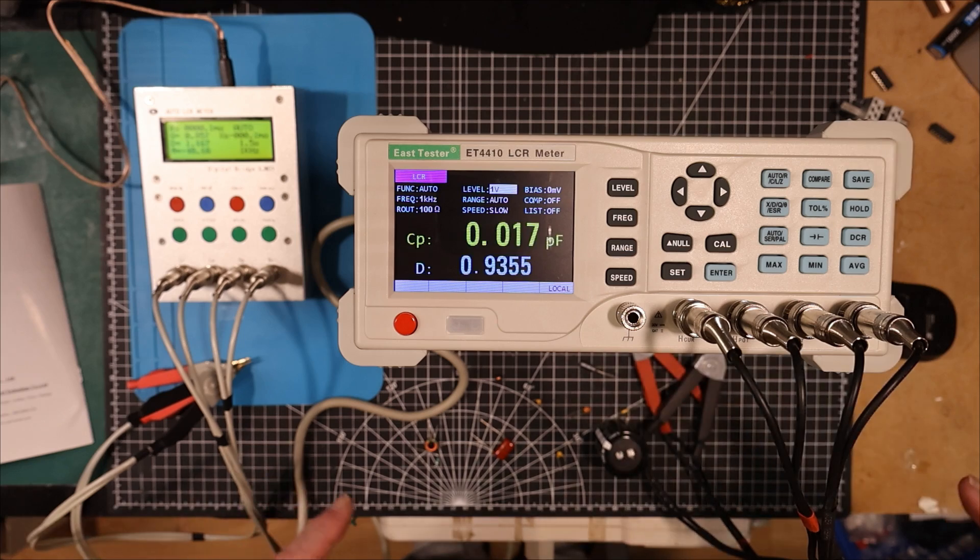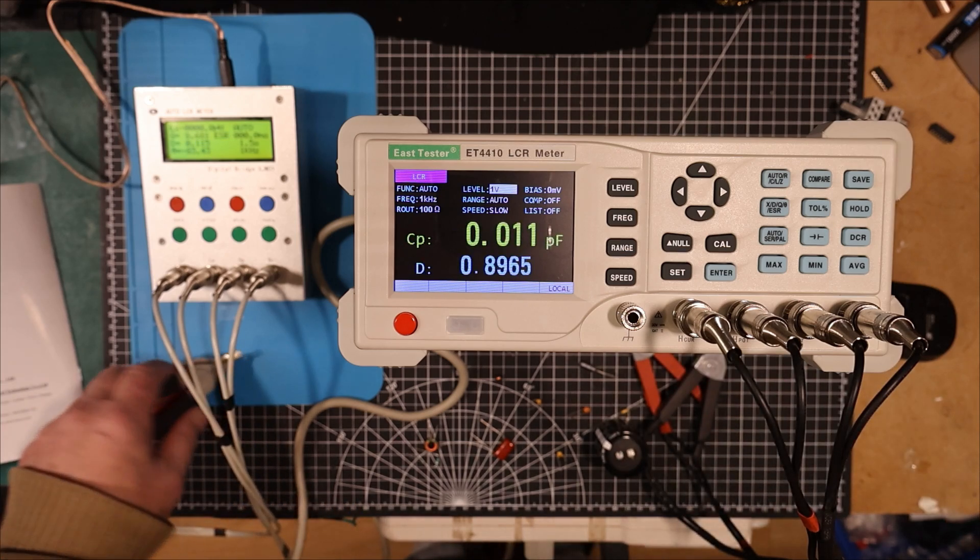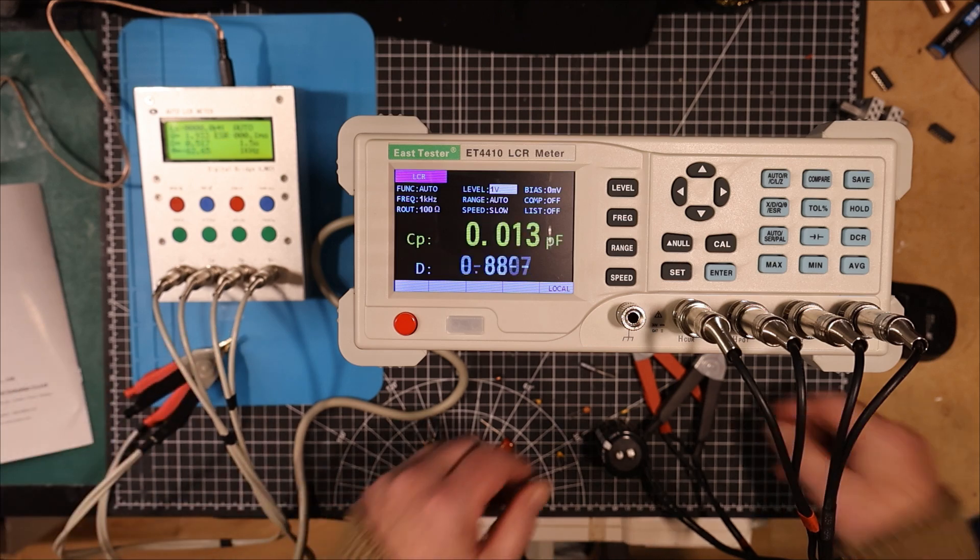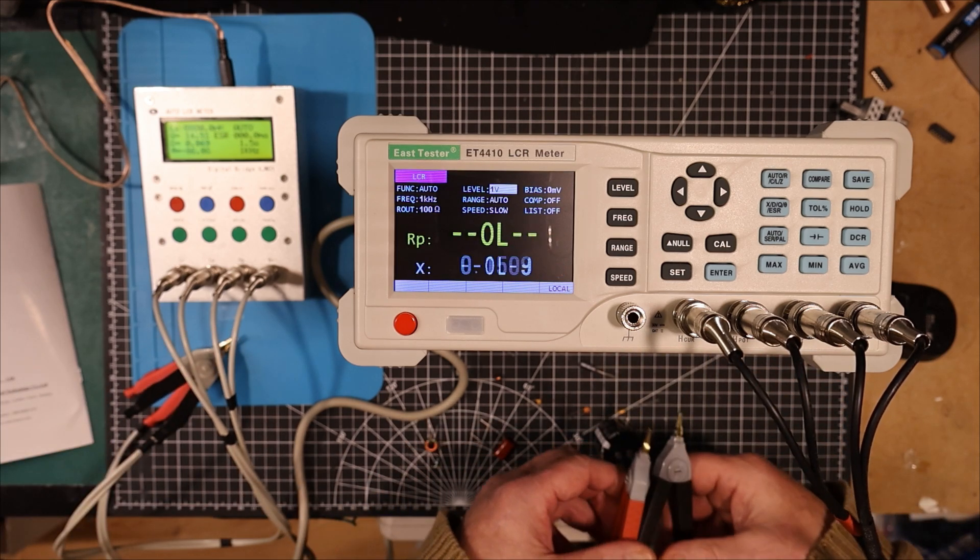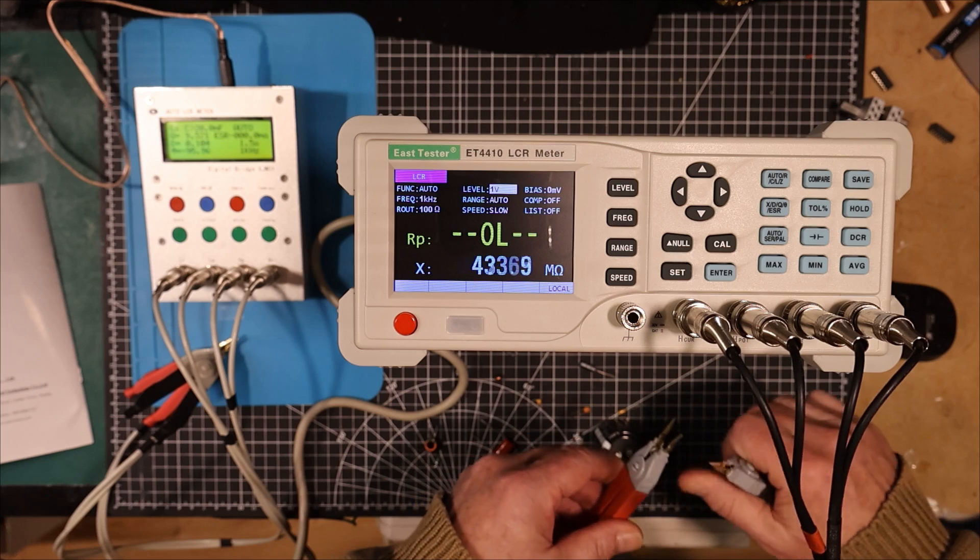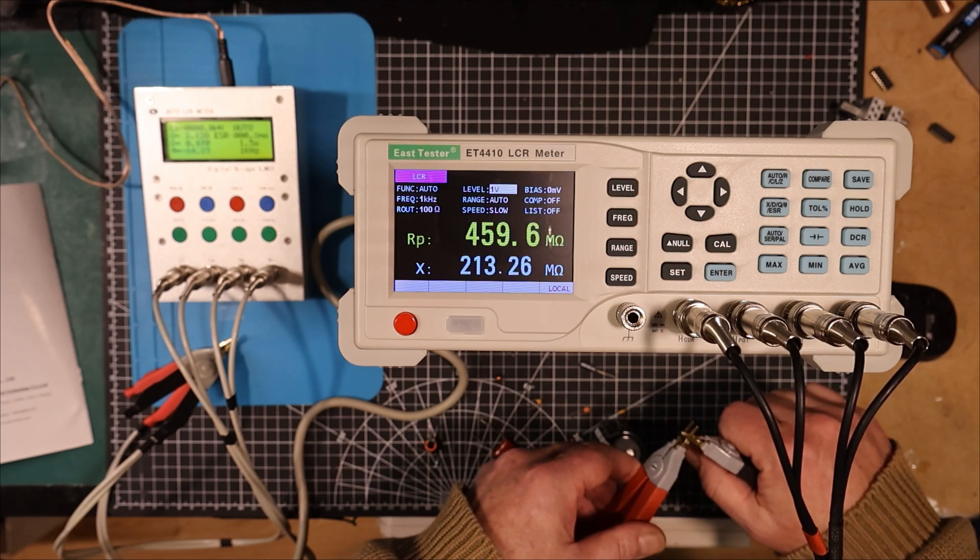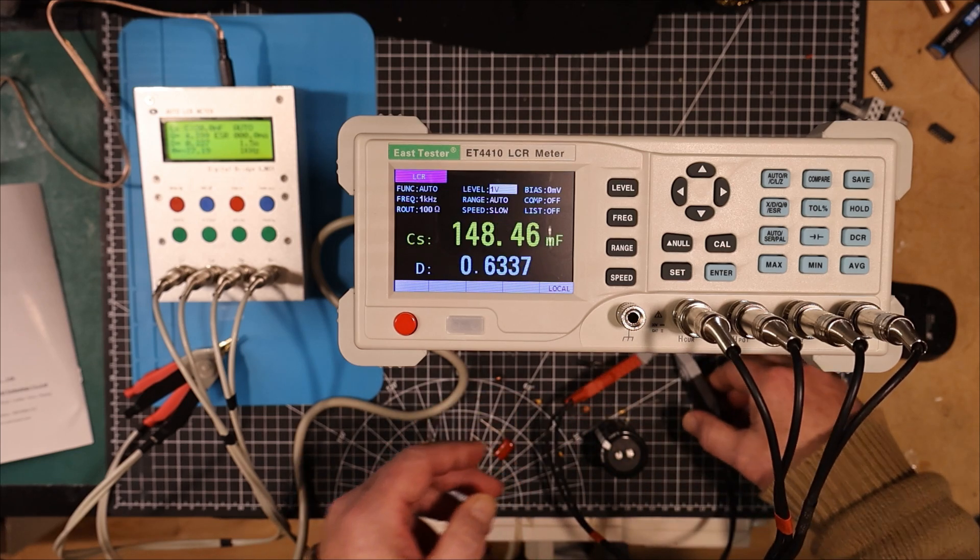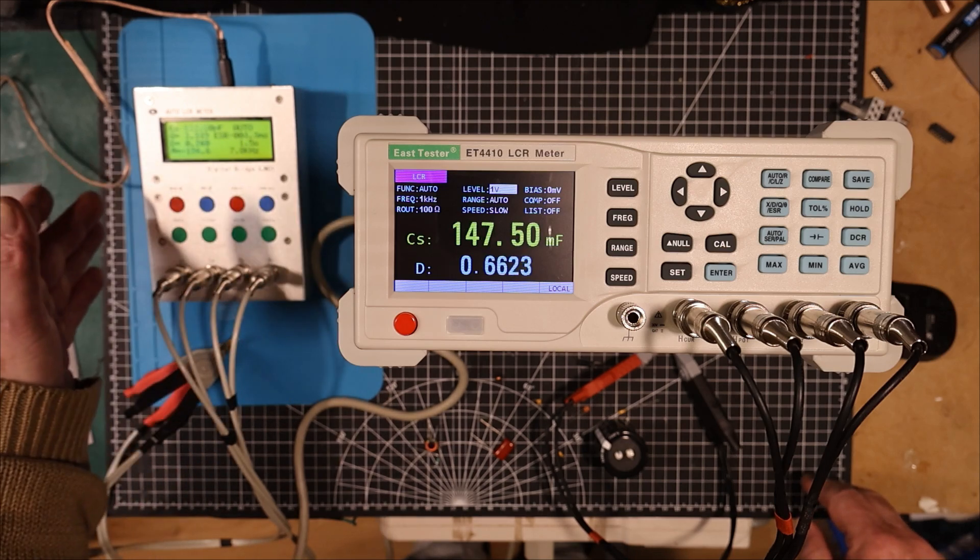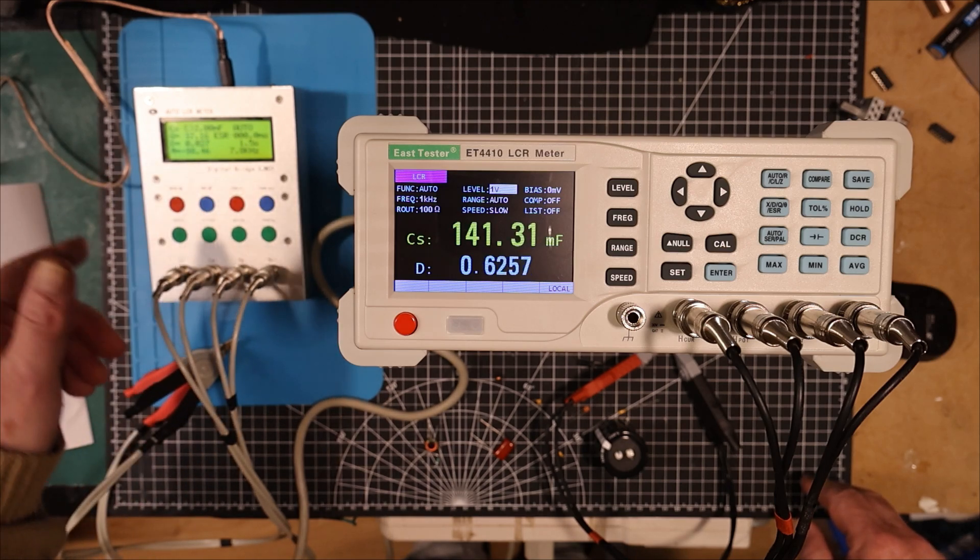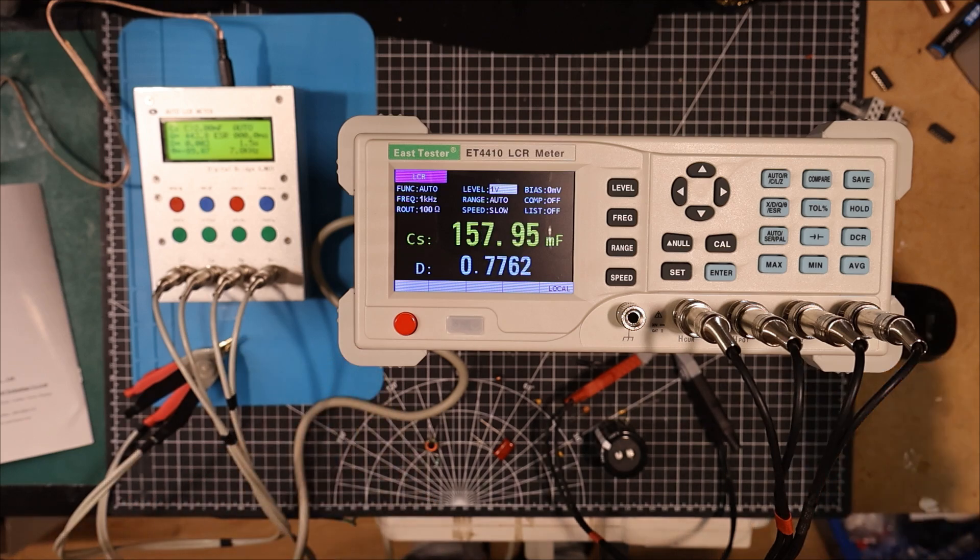What we have to do before we do anything else is we have to calibrate these. So I've got this one shorted. So let's try the short calibration first. So you do a short calibration, open calibration. And what they should do is they should run through various tests at all the available frequencies. Now this has only got three different frequencies.